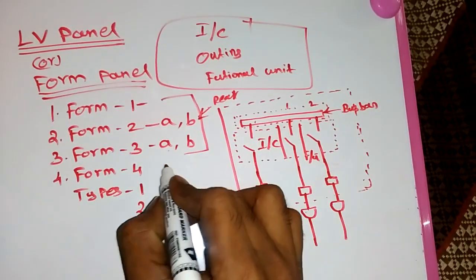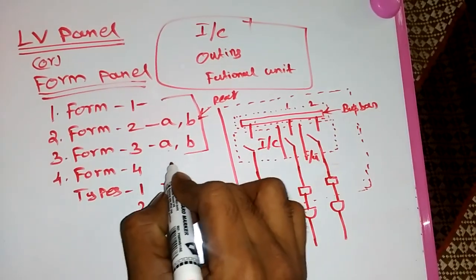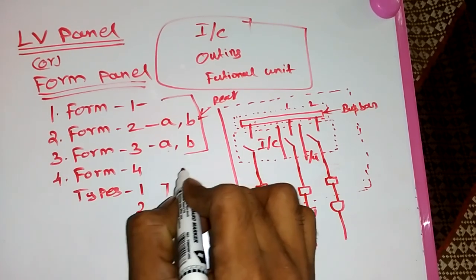In Form 3, same as before: bus bar not separate from terminals is called Type A; bus bar separate from the terminals is called Type B. Form 1, Form 2, and Form 3 are very rarely used in LV panels — these are very old versions.